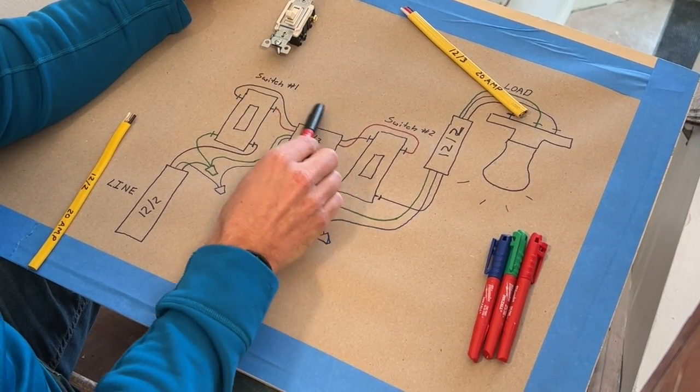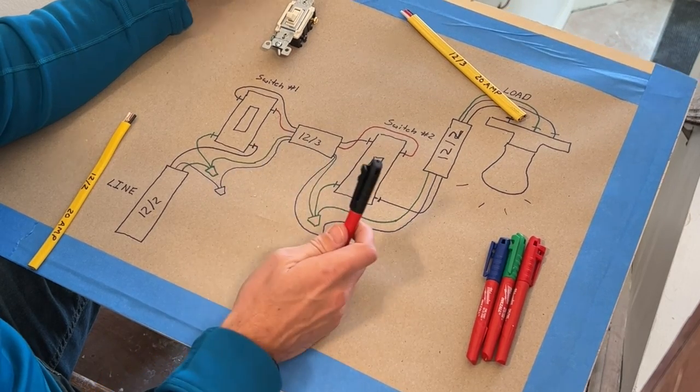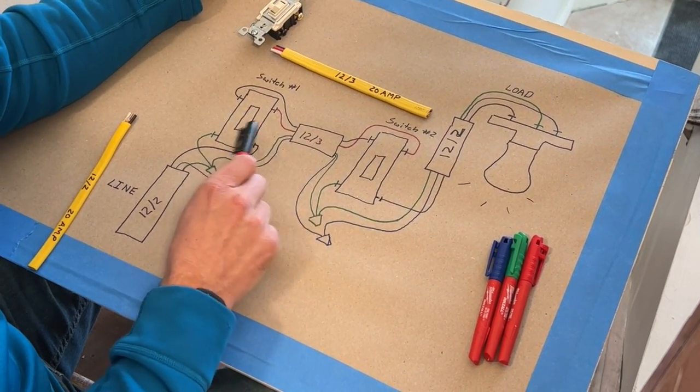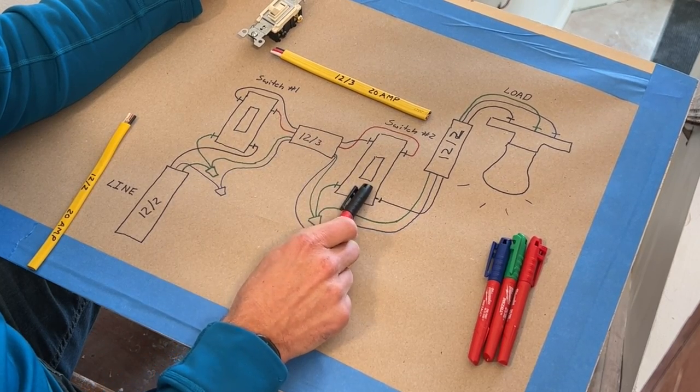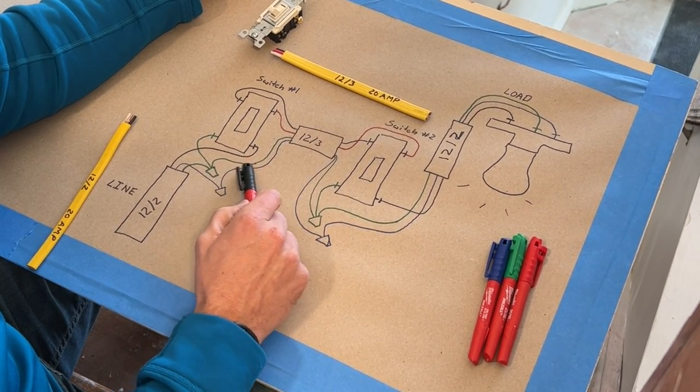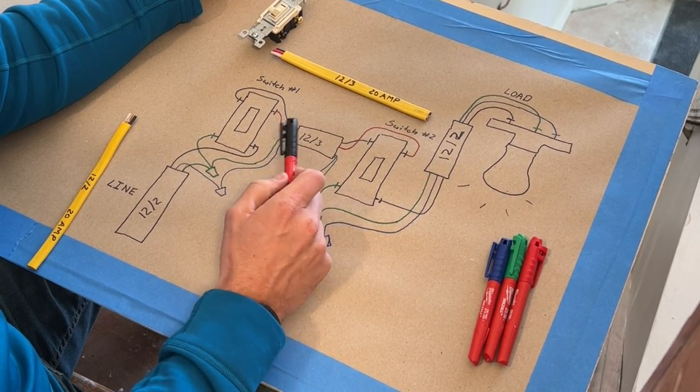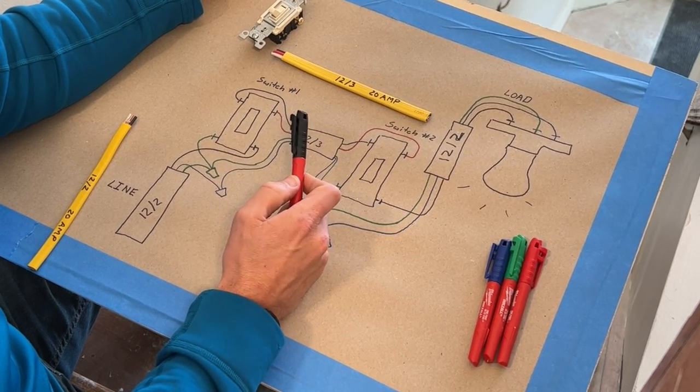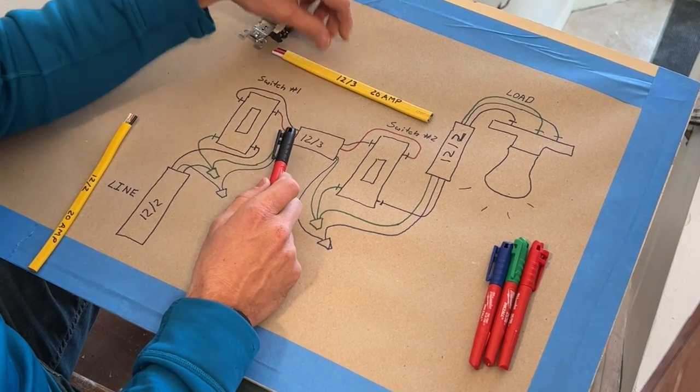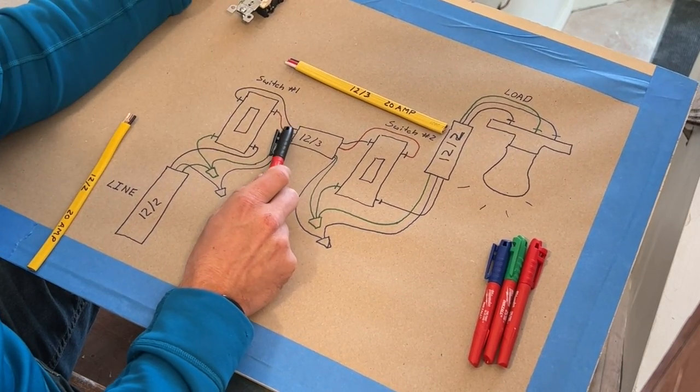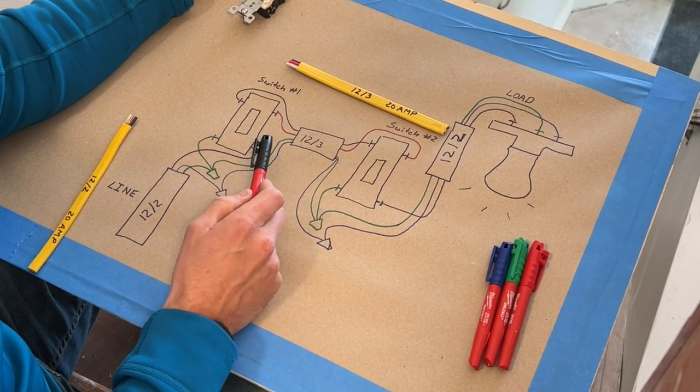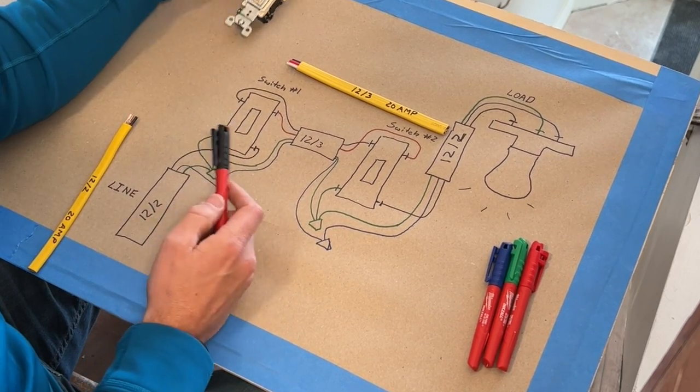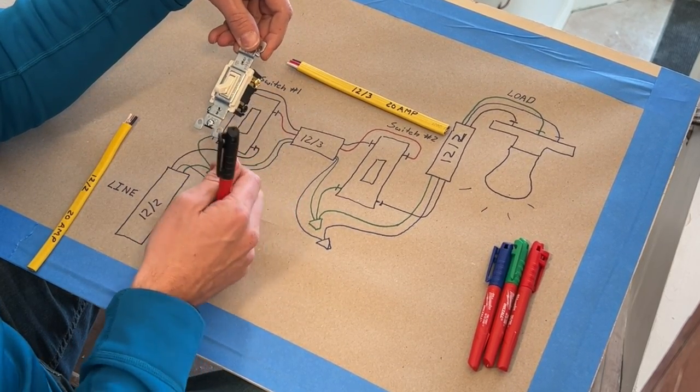And then we'd have 12-3 running between the two switches. Again, we passed the neutral - blue representing a white neutral wire. We passed ground as well. And then we'd take the red hot conductor and the black hot conductor, and we'd connect those up to these two terminals here. And these are our traveler wires.